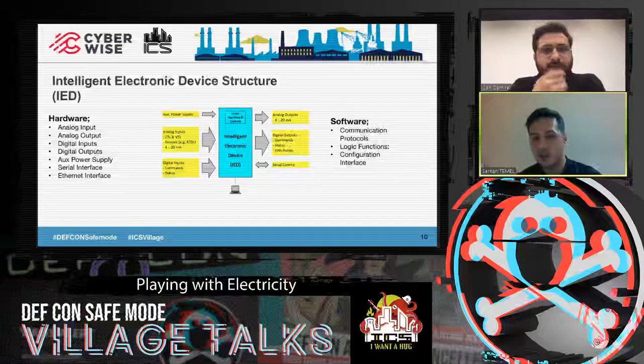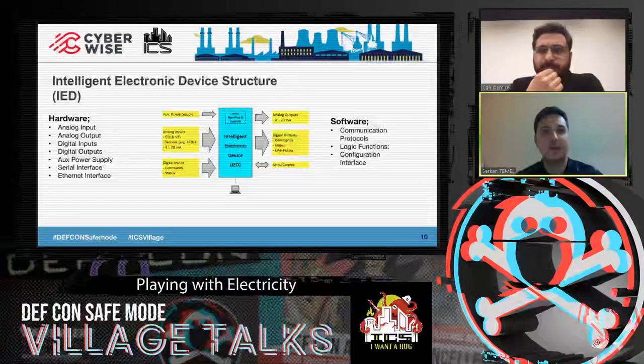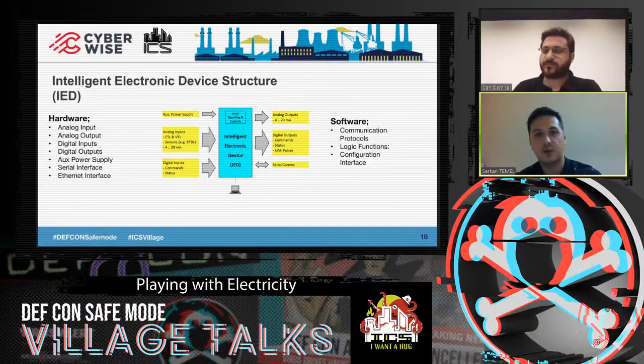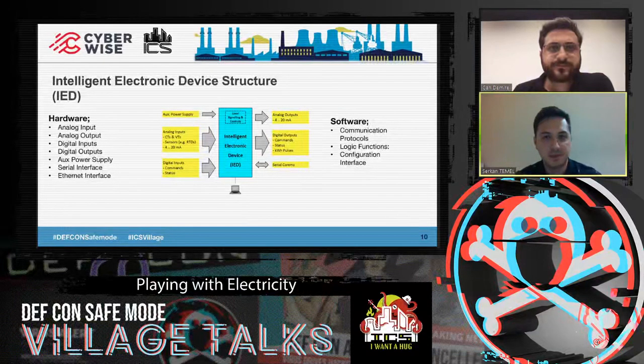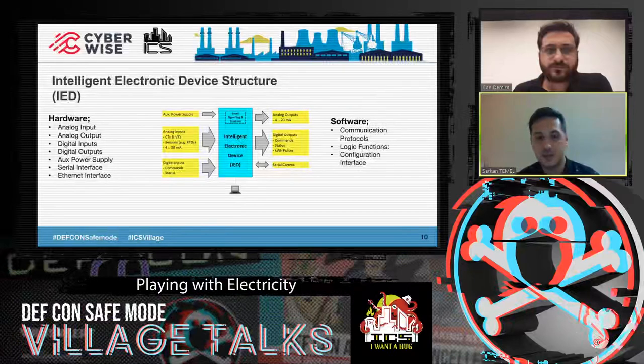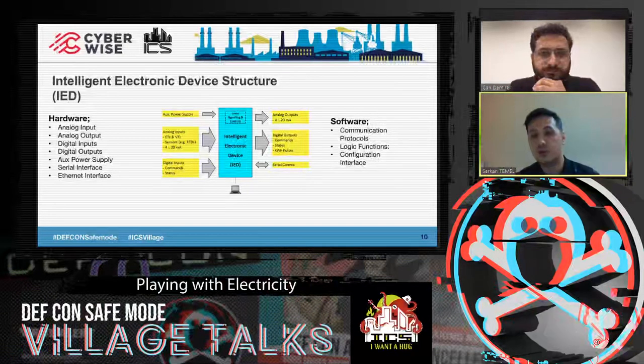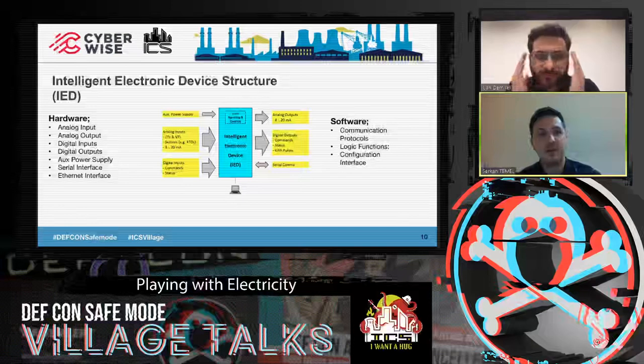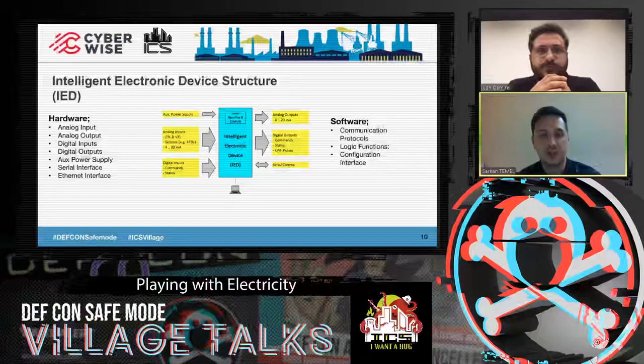On the software side, there are communication protocols, meaning industrial communication protocols like Modbus, Profibus, IEC 104, DNP3, and others. These help communicate with the RTU or with the SCADA systems to send information to the upper level. There are also logic functions to control things like the circuit breaker or other blocking functions, and a configuration interface. So this is the critical part of the IED device. As I mentioned, they have an Ethernet interface, and most IED devices nowadays use a web service interface for configuration software. So this is a vulnerability, the weak point of these IED devices nowadays.